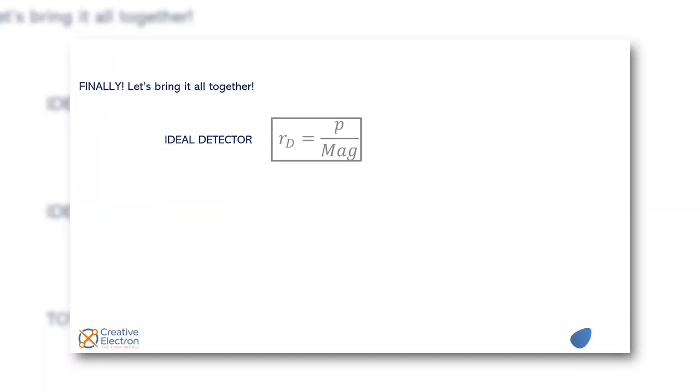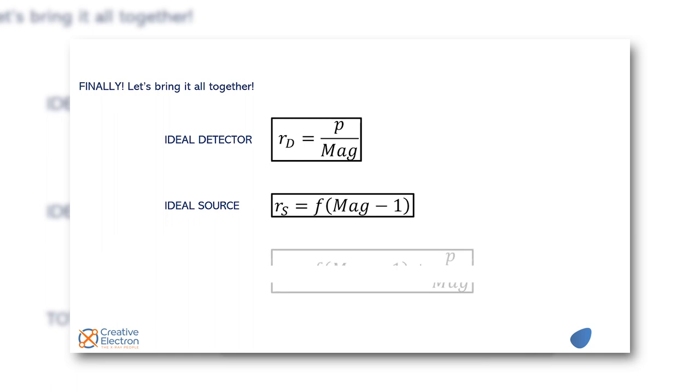So let's finally bring it all together, that's what we've been waiting for. Ideal detector we have that resolution is equal to p which is pixel size divided by magnification. Ideal source we're going to have that the resolution is equal to F which is the focal spot size on the source times magnification minus one. And put it all together we add it all, resolution is going to be F mag minus one plus p divided by magnification. So what does that look like in a real system?